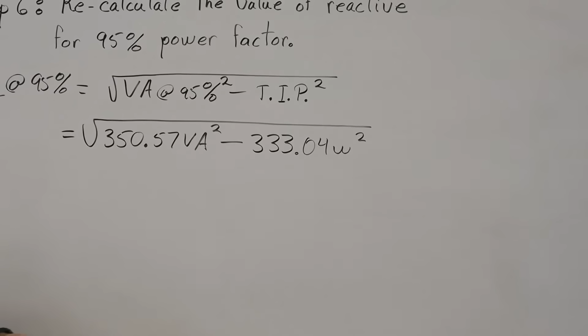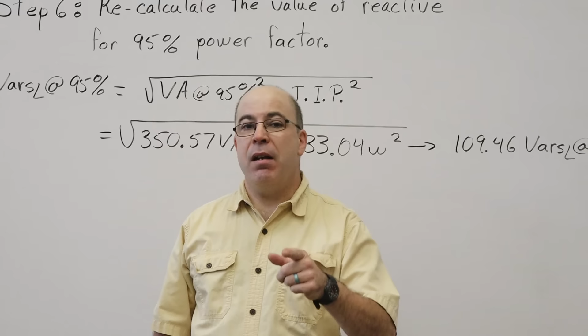Now the significance of this number is that this is the amount of reactive power I'm going to allow the motor to draw from my power supply. The remainder of that reactive power has got to come from my capacitors. So that's our next step - step 7, where we calculate how much reactive power I need to obtain from a capacitor.